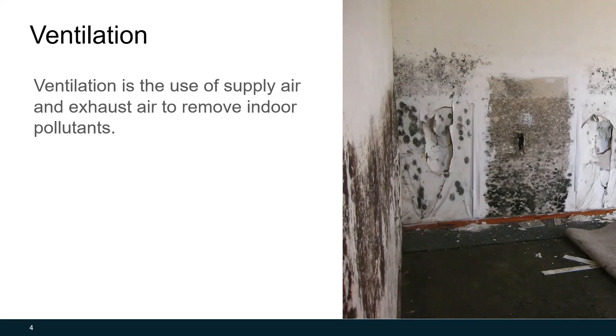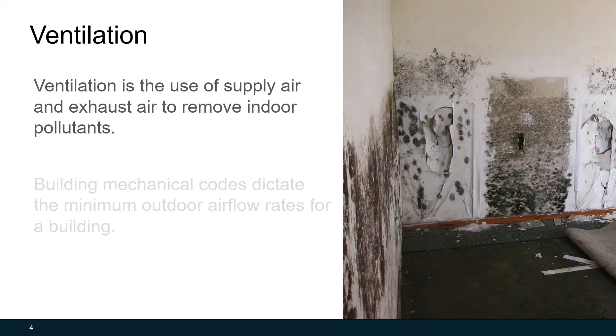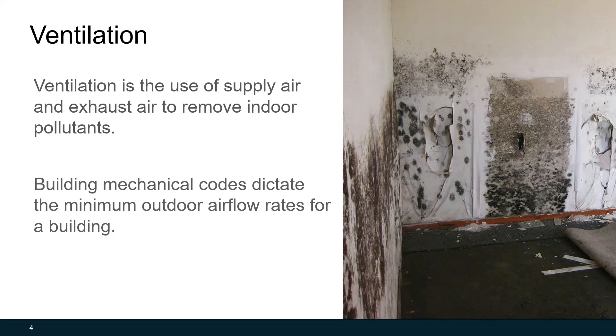In the 1970s, during the energy crisis, we reduced how much outdoor air or ventilation air that we brought into the building. We also sealed up the envelope, which limited the amount of natural ventilation. What happened because of that is people started to get sick in these poorly ventilated buildings. The World Health Organization defined the ailments that building occupants would get as sick building syndrome. Since then, building mechanical codes now dictate a minimum outdoor air flow rate for a building.